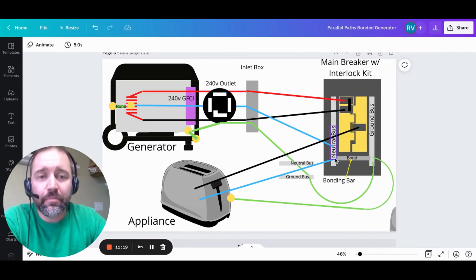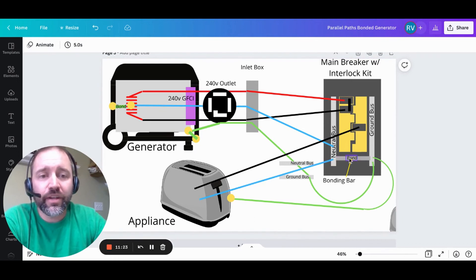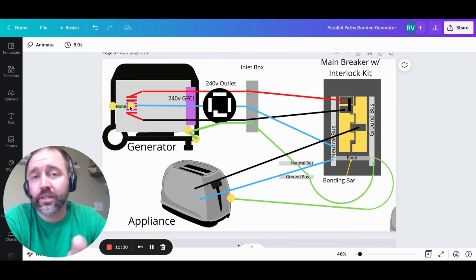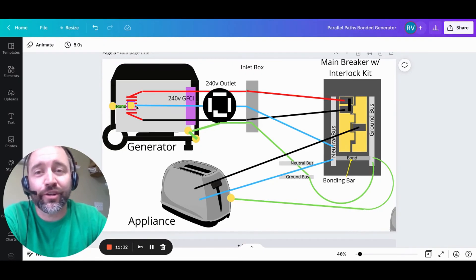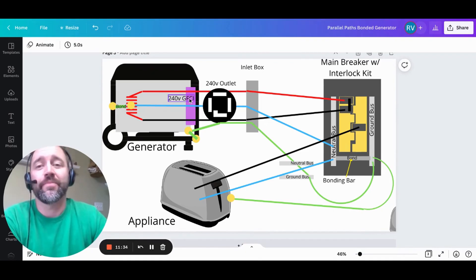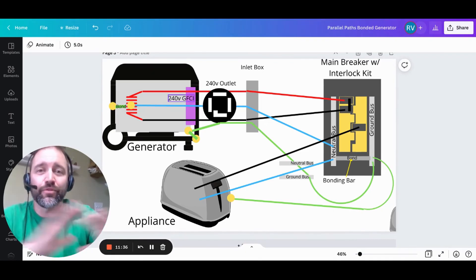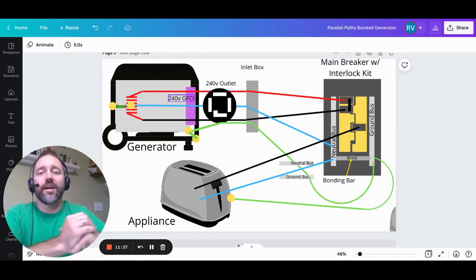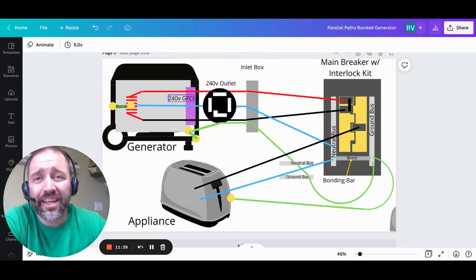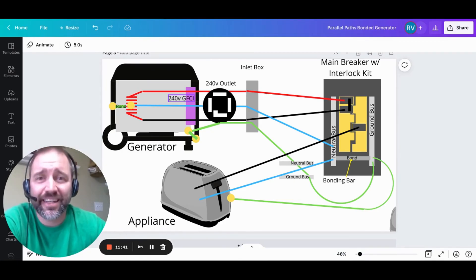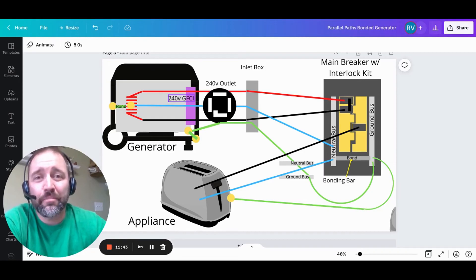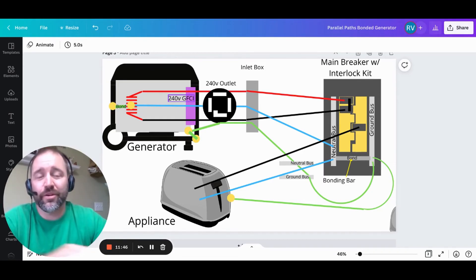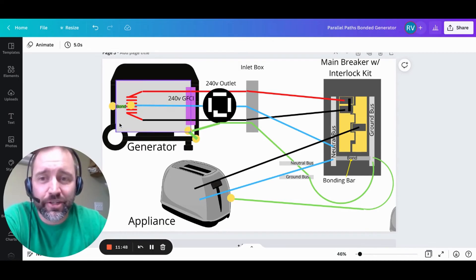And once again, maybe five of it flows back through here and maybe two of it jumps across this bond to the ground, follows the ground wire all the way back to the bond. Once again, where it completes the circuit, it just doesn't complete the circuit through the GFCI breaker. And once again, with that imbalance, it will trip it each and every time you try to do something. It will happen in a fraction of a millisecond before you even realize what's going on. Basically, you hook up your stuff and it trips, hook up your stuff and it trips, and you never get anything accomplished.